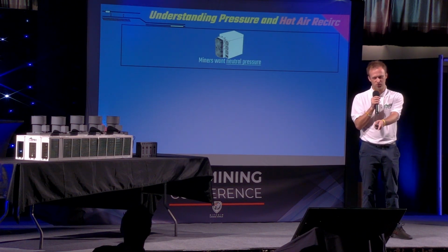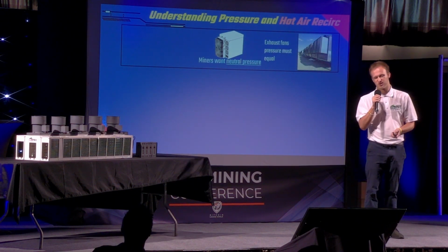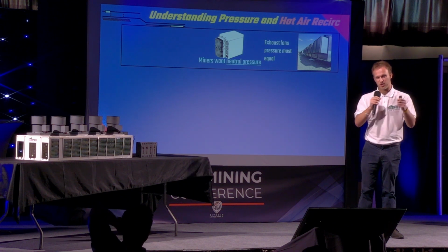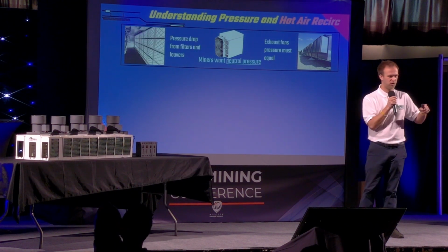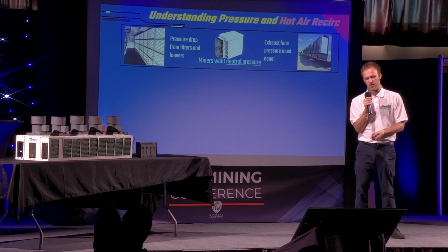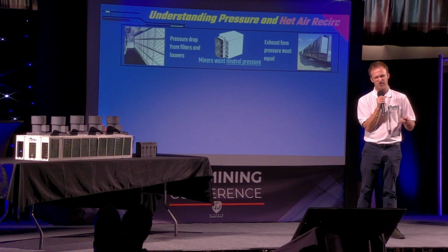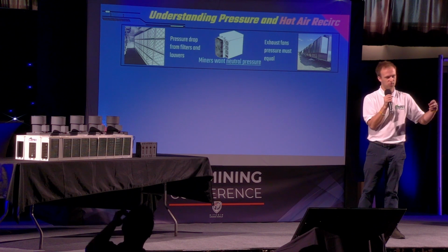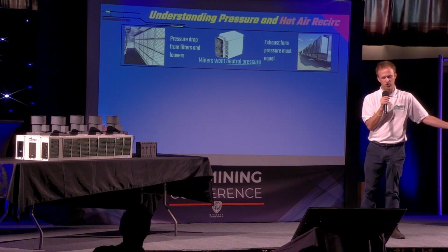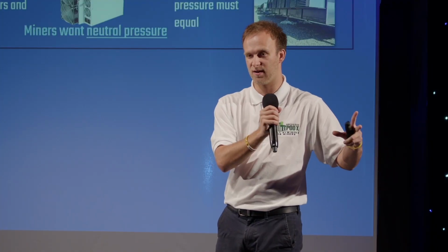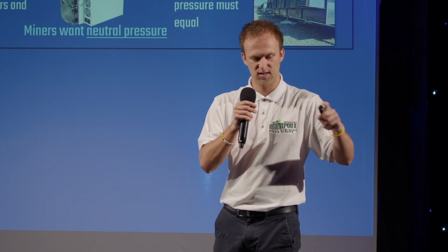So how do you get this neutral pressure on your miner? Well, it involves speccing your exhaust fans so that the pressure they are pulling is equal to the pressure drop across your intake. You can understand the pressure drop in your intake basically at your filter and louver level. You have restrictions and restraints from your filters and louvers. That creates a pressure differential that, when you add it up, your exhaust fans need to either slightly overcome or equal to make it neutral on both sides of your miner. If you can do that, your miner is going to be happy, its fans are going to run without restraint, and it'll run a lot longer and at higher temps throughout your mining cycle.